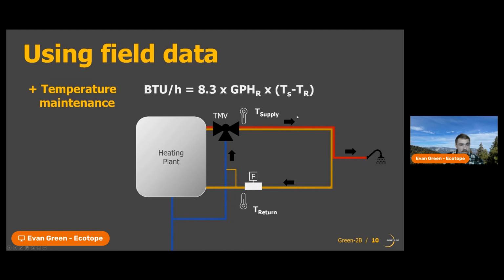And one thing we've noticed after we've gathered temperature maintenance data on several different buildings is we've actually gotten short points of time where we're measuring negative temperature maintenance losses. And we know that there's no one in the building with a blowtorch up to these pipes or anything, or shoving heat back in these pipes. But what we realized is sometimes this thermostatic mixing valve isn't supplying a really constant supply temperature. So if we see this supply temperature spike, for instance, then we're going to see a spike in water temperature right here. But this water that has spiked in temperature hasn't made it all the way around the loop yet.